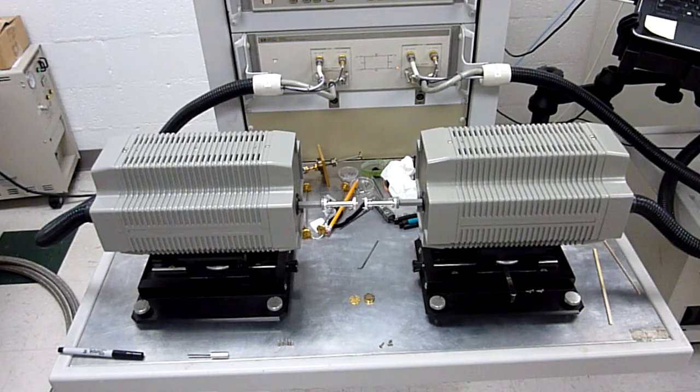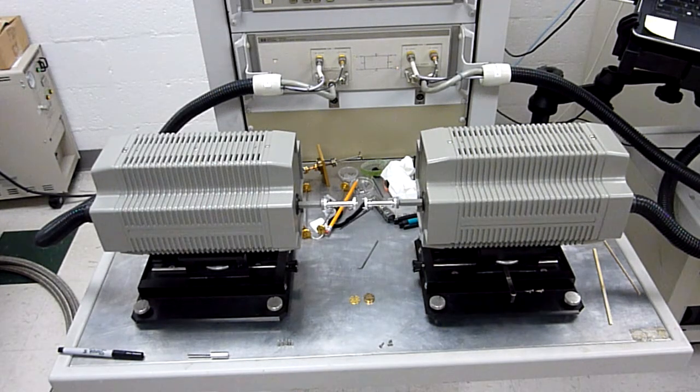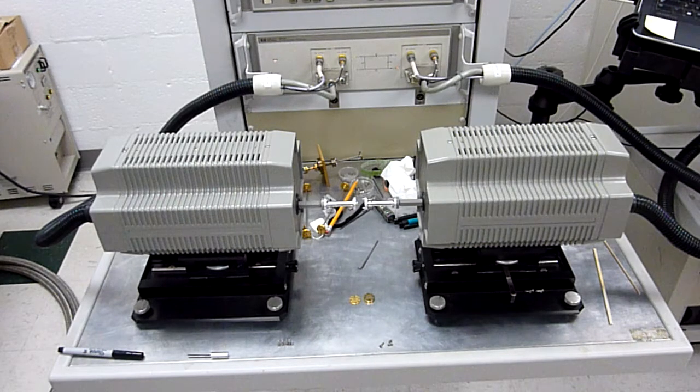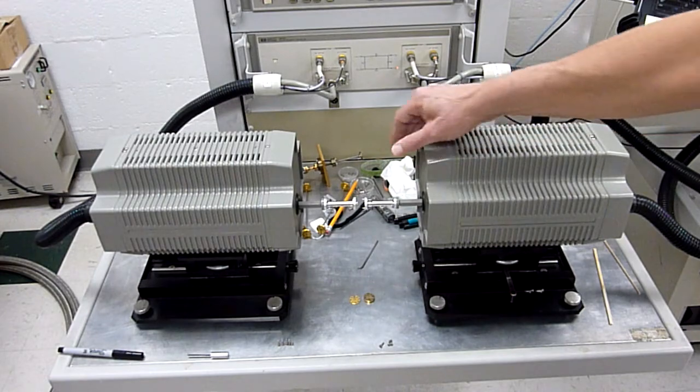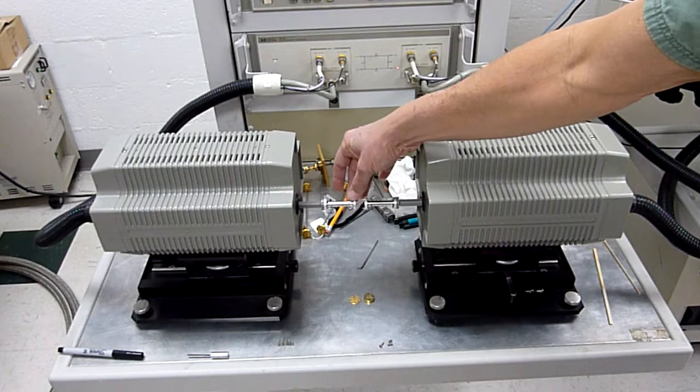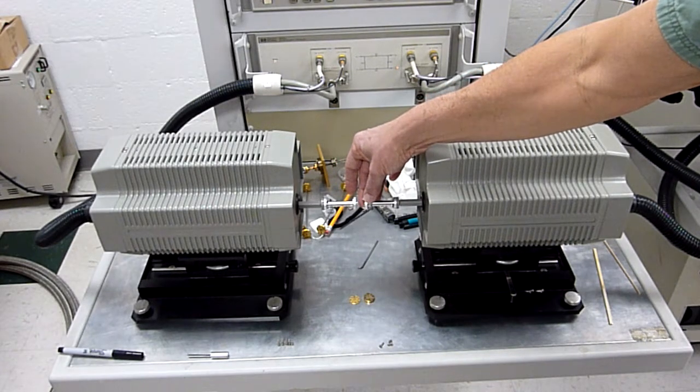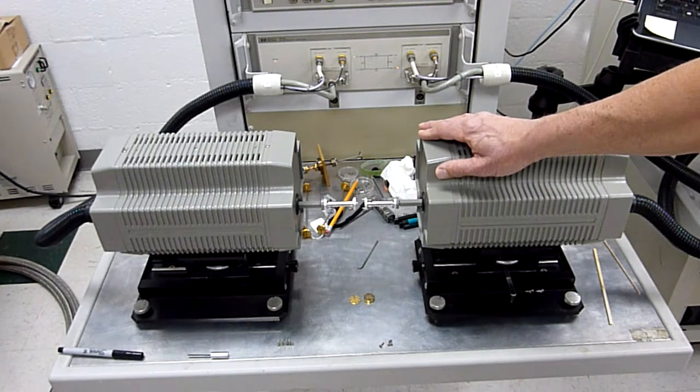Now those are actually two quality pieces that are in very good condition, but we were using two shorter pieces of waveguide at that point. And I'll try to tie in a photo later on, but those two pieces of waveguide were actually quite damaged at the output or the input flanges here. You really couldn't tell it until you looked under the microscope how much damage there was.